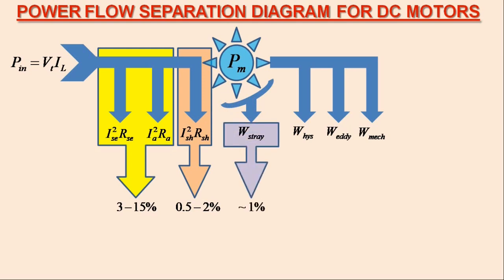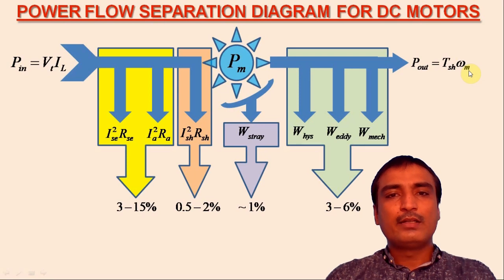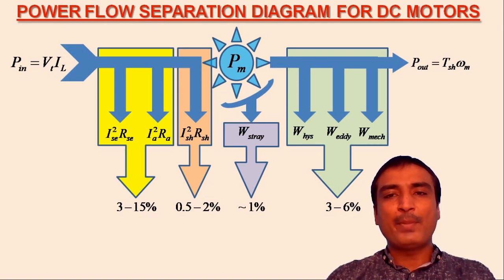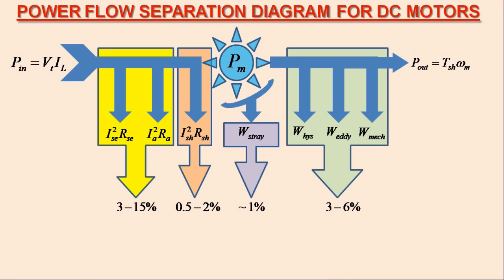After subtracting all these rotational losses from the mechanical power developed by the armature, one may finally have the net mechanical output power, which is equal to the product of torque T_SH at the motor shaft and mechanical speed omega_m of the rotor. The series field winding copper loss and armature circuit copper losses — including interpole winding copper loss, compensating winding copper loss and brush contact loss — together are called the variable losses in the DC motor.